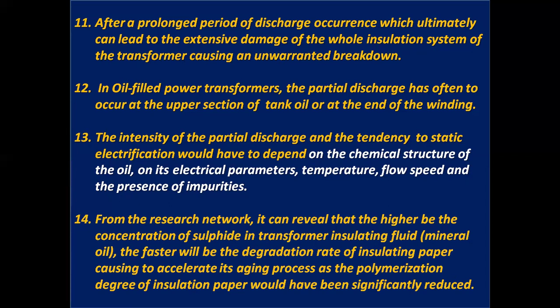Number 14, research reveals that the higher the concentration of sulfide in transformer insulating fluid, that is mineral oil, the faster the degradation rate of the insulating paper, accelerating its aging process as the polymerization degree of the insulation paper is significantly reduced.